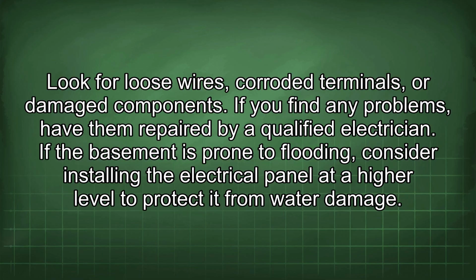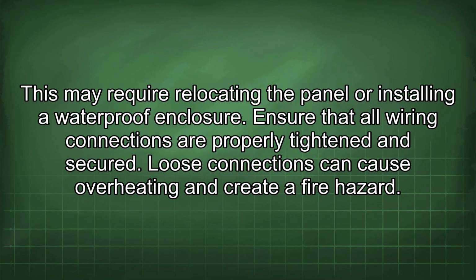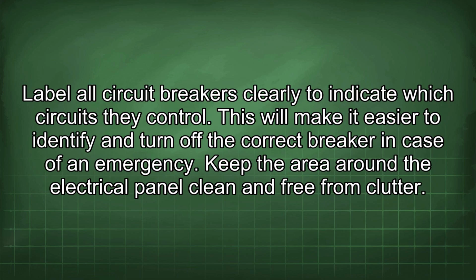If the basement is prone to flooding, consider installing the electrical panel at a higher level to protect it from water damage. This may require relocating the panel or installing a waterproof enclosure. Ensure that all wiring connections are properly tightened and secured. Loose connections can cause overheating and create a fire hazard. Label all circuit breakers clearly to indicate which circuits they control. This will make it easier to identify and turn off the correct breaker in case of an emergency.